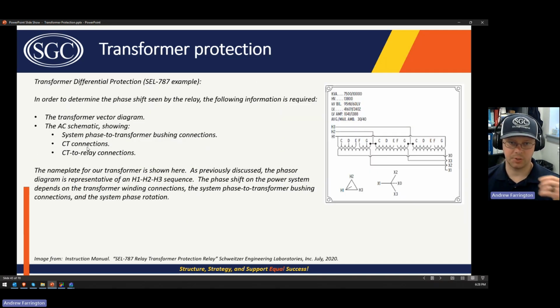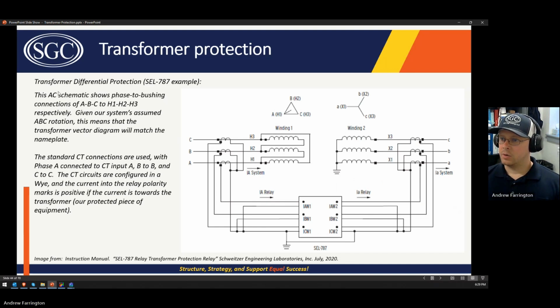You also need to know what the CT connections are, whether it's a Y configured CT or a delta connected CT, and whether or not those CTs are actually connected where phase A is into the A input, like we talked about. And yeah, the CT to relay connections, which is what I was just saying. So for the transformer we have, the connections are A to H1, B to H2, and C to H3, which is very simple. And then the phase shift depends on those connections. I'm just going over that again here in more detail. I guess I should scroll through the slides before I start trying to ad lib and talk about it. So very simple.